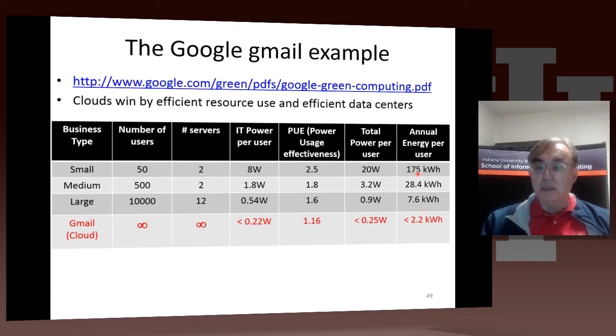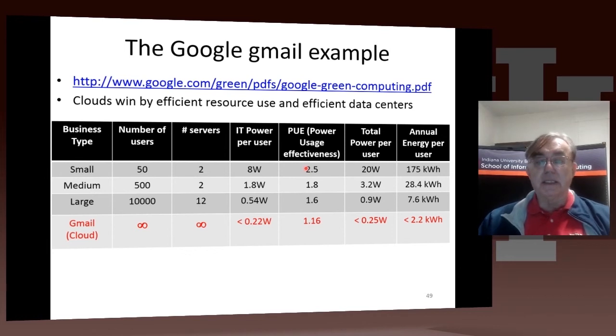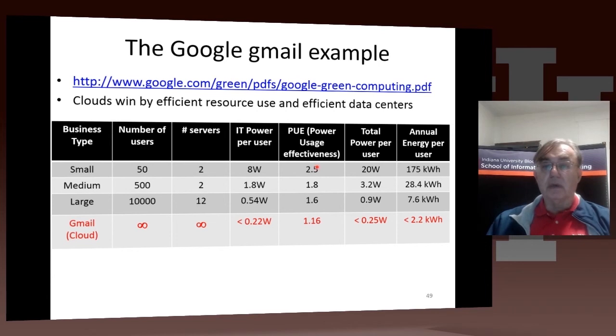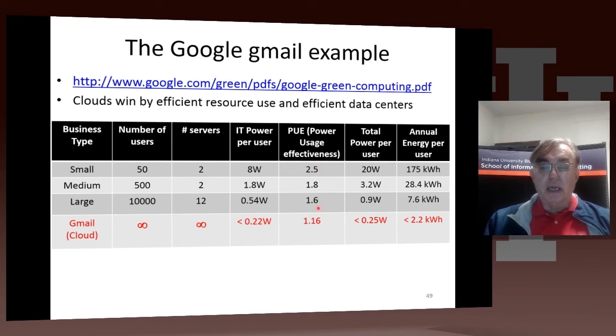This is just due to the economies of scale, but also just to the data center itself. There's the Power Usage Effectiveness (PUE), which says that if the power use is exactly the power needed by the CPUs or servers, that's a PUE of one. If it's 2.5, it means you're using 2.5 times as much power for your data center as what you need for the servers — so that's not satisfactory. And you can see modern clouds here down at 1.16.